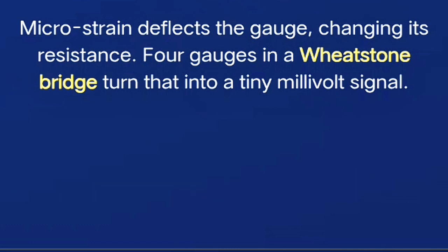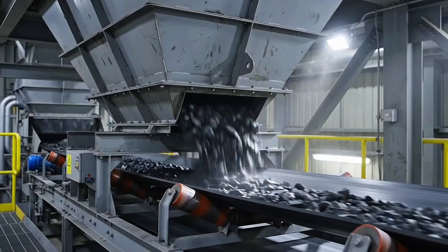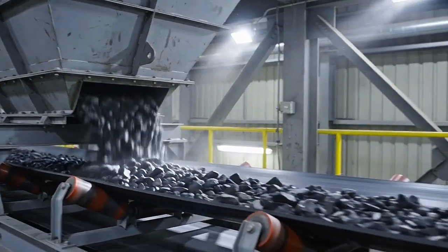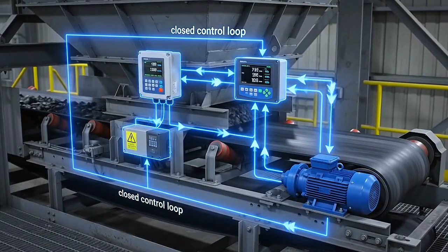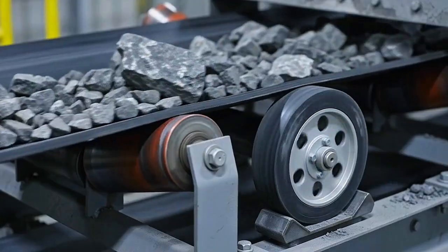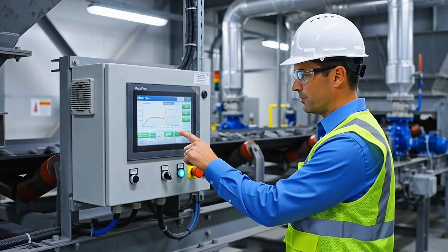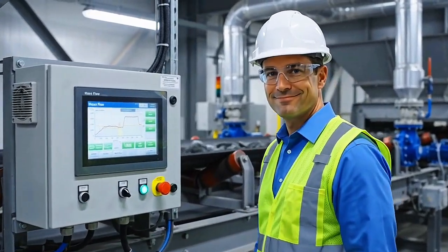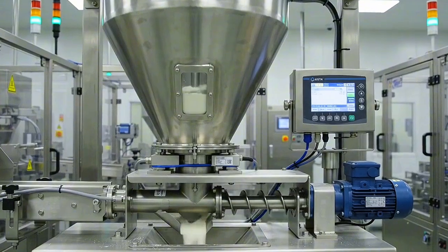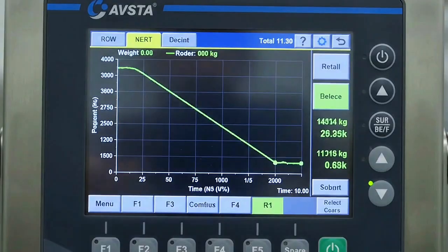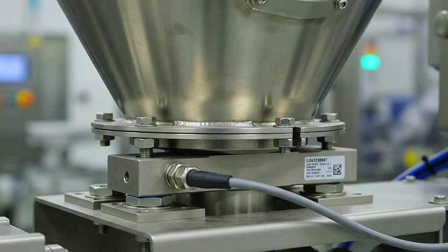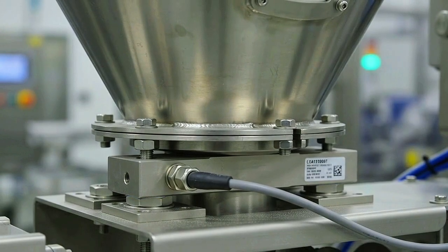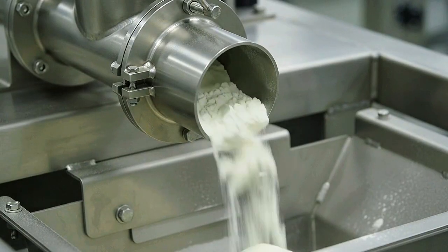Let me walk you through where this shows up on your plant, because we'll cover each of these in depth as separate videos. Belt weigh feeders sit under raw material bins and coal bins, weighing material on a moving belt in real time and controlling belt speed to hold a mass flow set point. This is a closed control loop, and it's probably the weighing system you touch most often. Loss in weight feeders, common on additive and minor ingredient dosing, where the whole hopper sits on load cells and the controller doses by watching the weight drop over time, not by watching a belt.